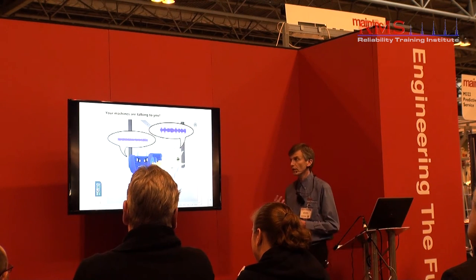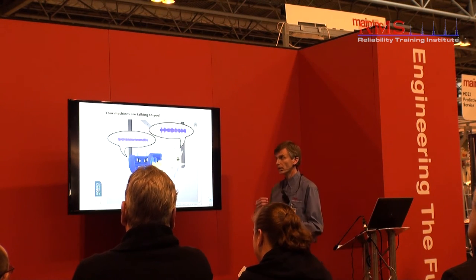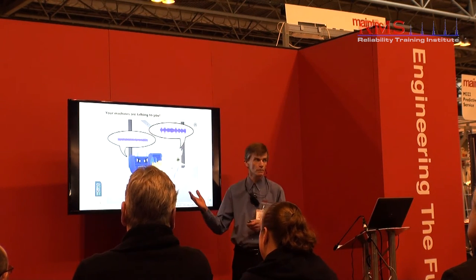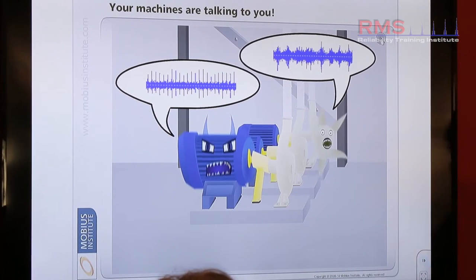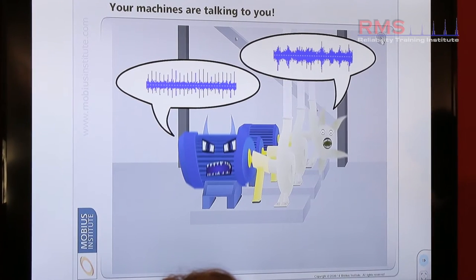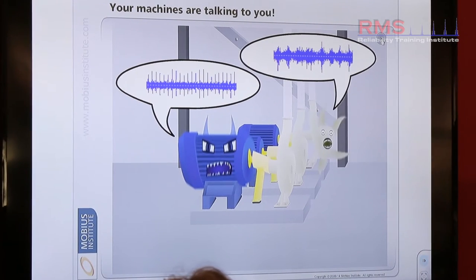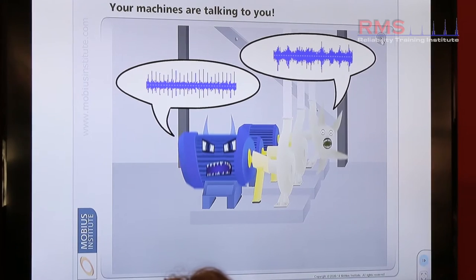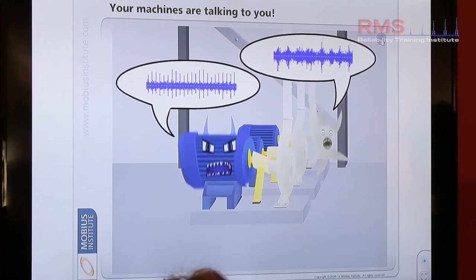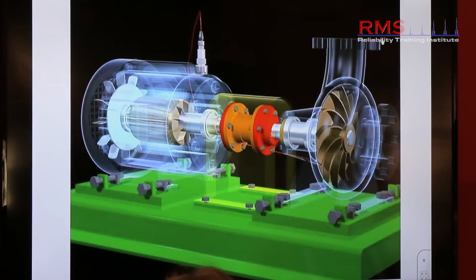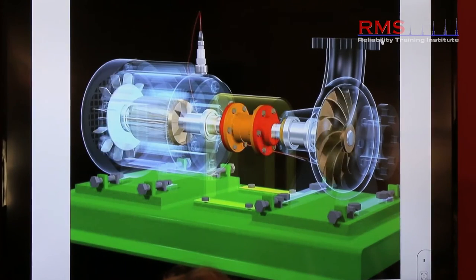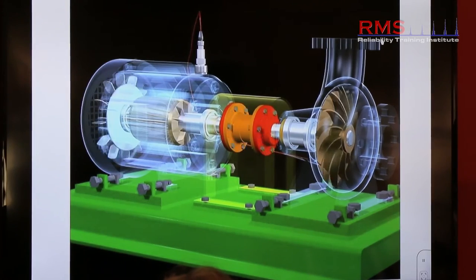With vibration monitoring, we can measure the signals, we can measure the height of the signal, and we can measure the distance — how long each event takes — to understand which component in the machine is problematic. So we can narrow it down to a specific component within the rotating asset.